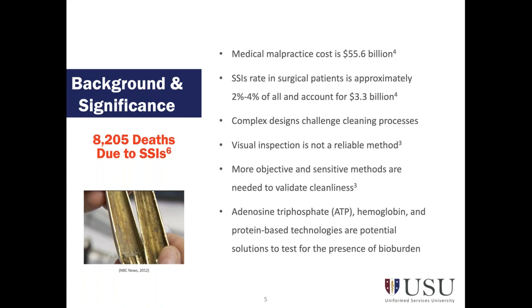Now, for most of you that have seen a Yankauer before, think about how that design works. It's a very simple instrument, but think about the fat part of the instrument, which is the handle, and where the suction line is connected and where the suction tip is. Imagine cleaning that instrument, and most of you probably have already done it. There's only one size of brush you can pick to go through either end, and both ends are smaller in diameter than the actual handle size. So if you introduce a brush through that instrument, you will be doing nothing to that particular area of the instrument. And if you think that the ultrasonic washer will take care of that, good luck.